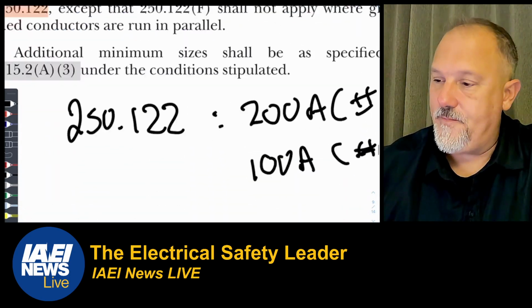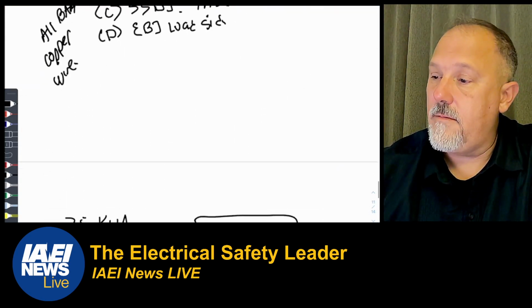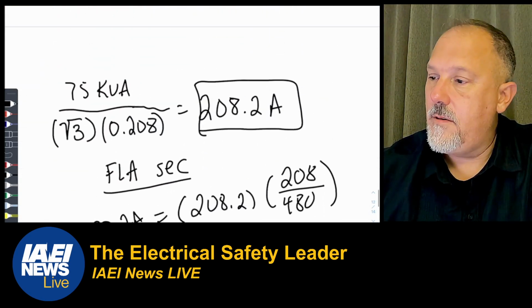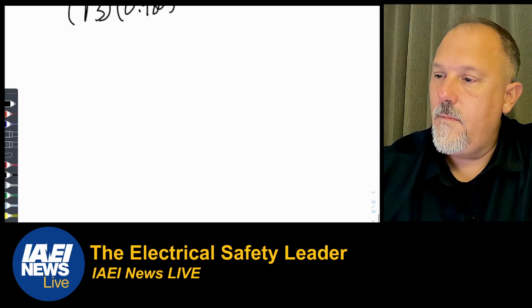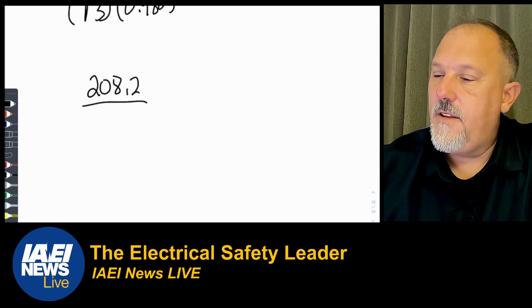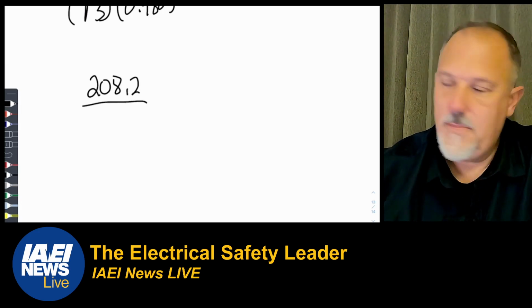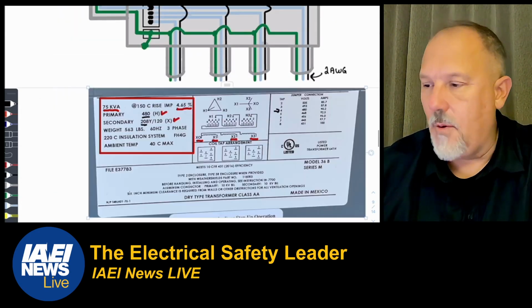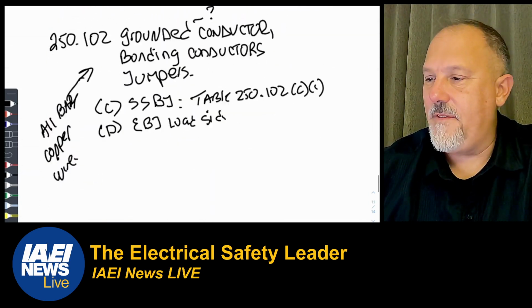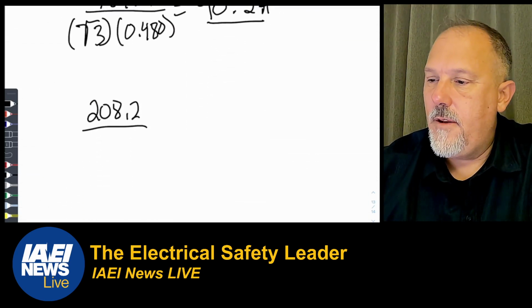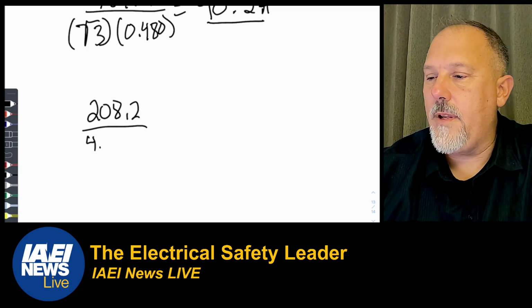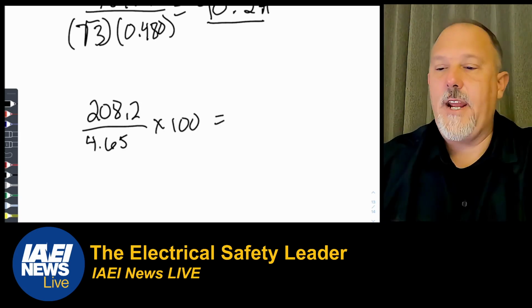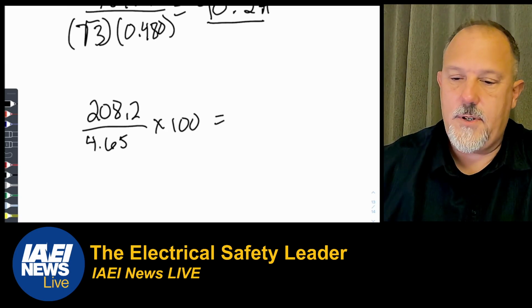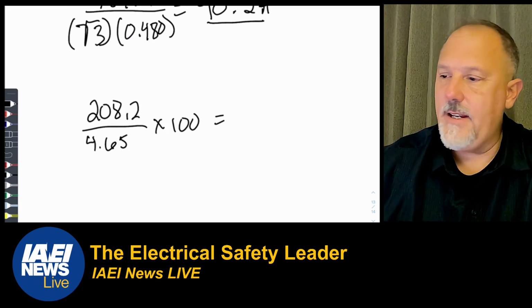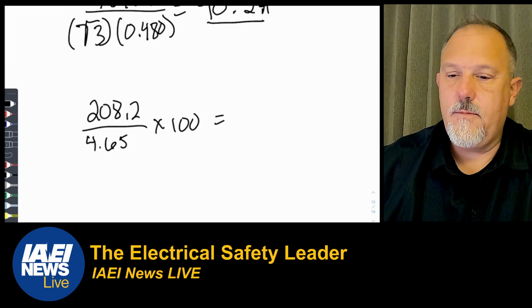So 4.65. I take the secondary full load amps, which was 208.2, divided by the percent impedance. What was the number? 4.65. So I do 4.65, and then I multiply that by 100. So get your handy dandy calculator out. 208.2, 4.65 divide, 100 multiply.